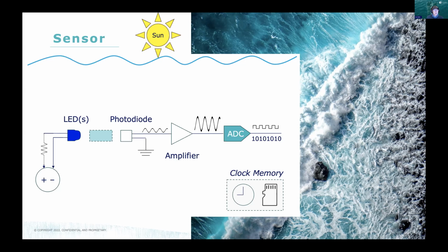So we'll just be looking at the most simple sensor configuration. And just as a note in the lower left, you see that in general, we don't just power on the LED while the instrument's on. It actually flashes, not just at the rate that you see, because that's when it's turning on different LEDs in the ECO, but it's actually modulated. It's turned on and off at about 1,000 times a second.